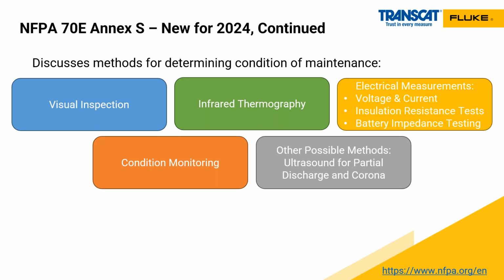And then battery impedance testing. Battery impedance testing really gets into testing on the live circuit or battery string. Keep in mind that a battery, if it's live, is outputting DC voltage. I can't do an ohm measurement on that live, so I have to use what's called impedance measurement. Resistance is DC, impedance is AC testing, and we're able to inject an AC voltage signal through the terminals to look at the internal impedance or resistance of the battery cells, the floating voltage, and even the temperature.